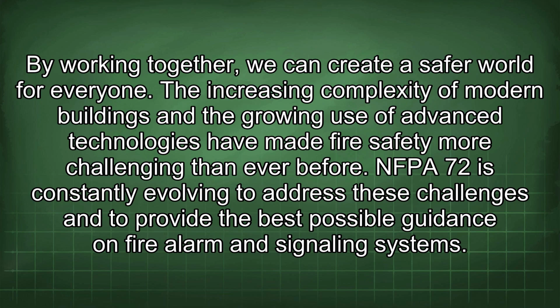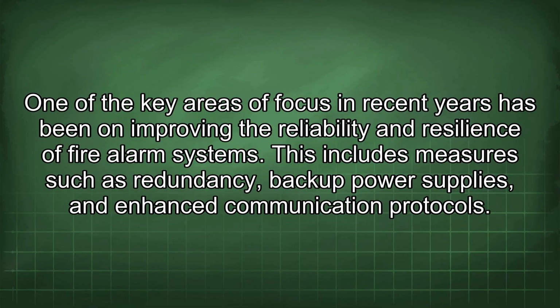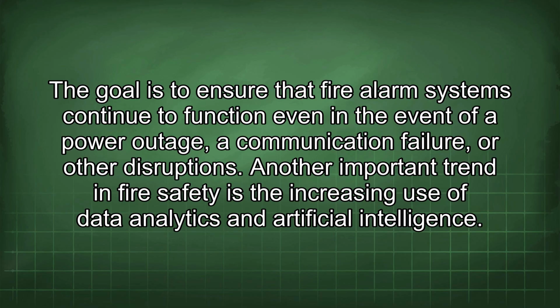The increasing complexity of modern buildings and the growing use of advanced technologies have made fire safety more challenging than ever before. NFPA 72 is constantly evolving to address these challenges and to provide the best possible guidance on fire alarm and signaling systems. One of the key areas of focus in recent years has been on improving the reliability and resilience of fire alarm systems. This includes measures such as redundancy, backup power supplies, and enhanced communication protocols. The goal is to ensure that fire alarm systems continue to function even in the event of a power outage, a communication failure, or other disruptions.